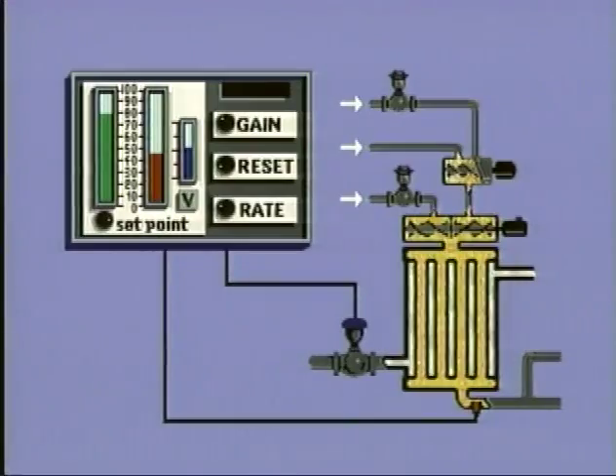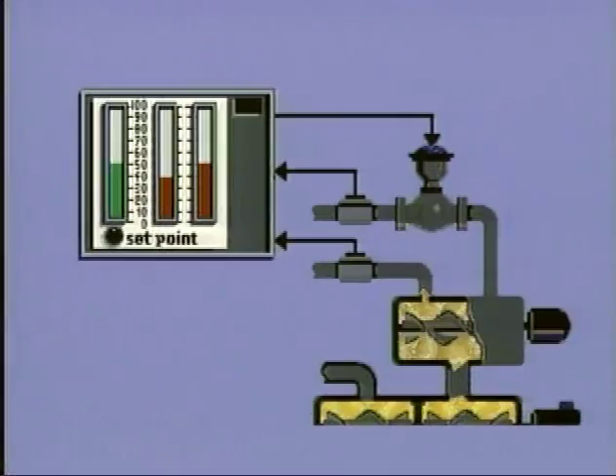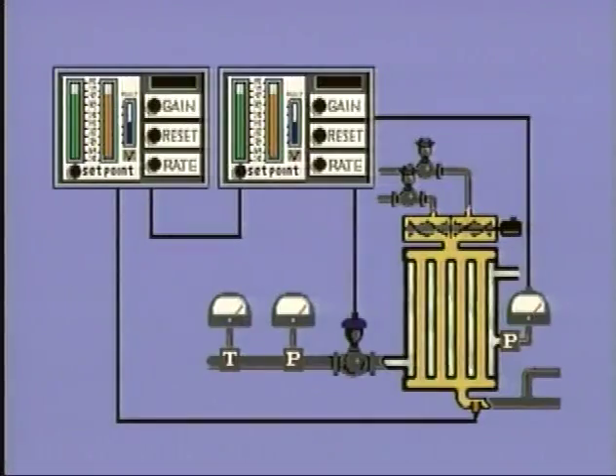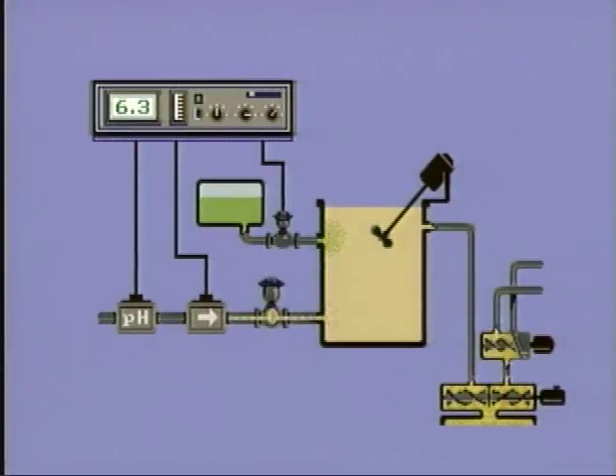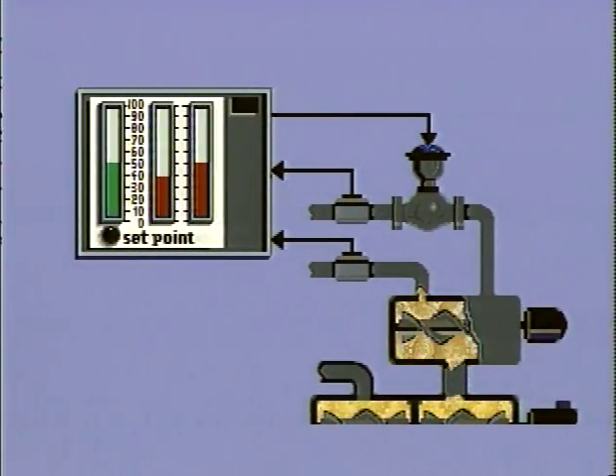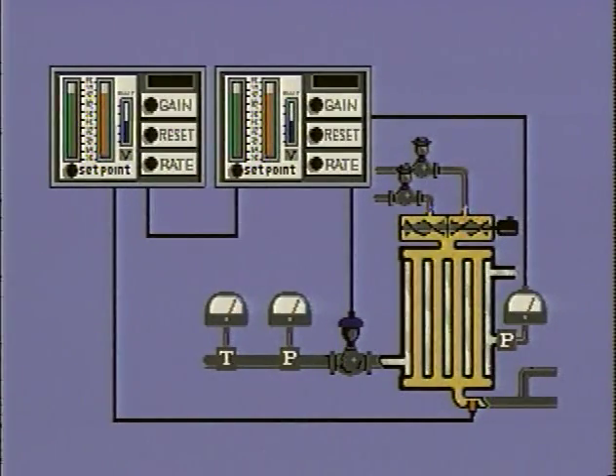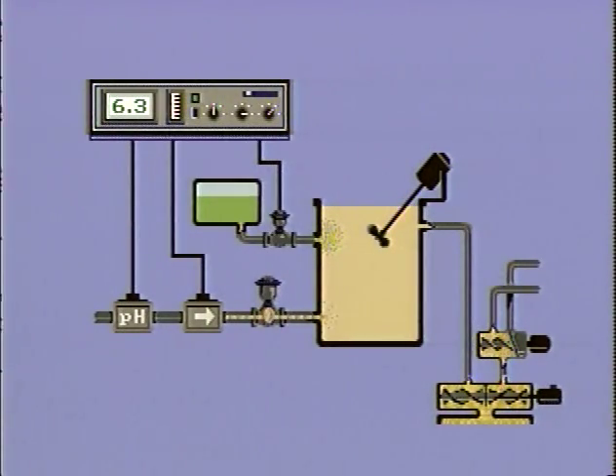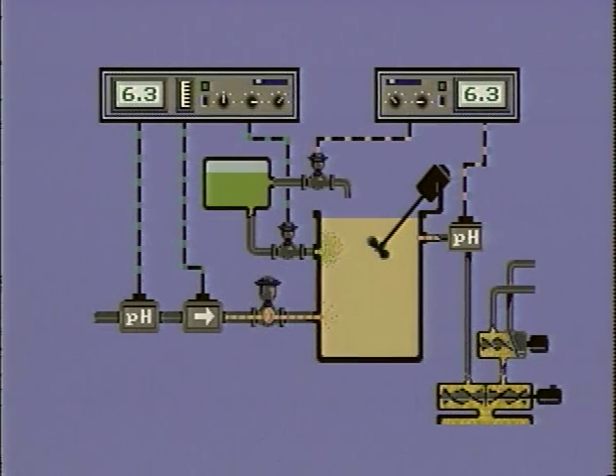We've now seen how the chemical company's control systems have evolved along with changes in the production system and, indeed, along with changes in the business environment. These systems have evolved from the basic feedback system using a PID controller to include entirely new control concepts. First, with ratio control, input from one flow stream was used to adjust another flow stream, maintaining a constant ratio between the two streams. Second, with cascade control, two feedback loops, one within the other, were used to minimize temperature variations. Third, with feed-forward control, disturbances in pH were compensated for before they had a chance to affect the system. And fourth, with adaptive control, a controller adjusted its response automatically to compensate for non-linearities in the process.